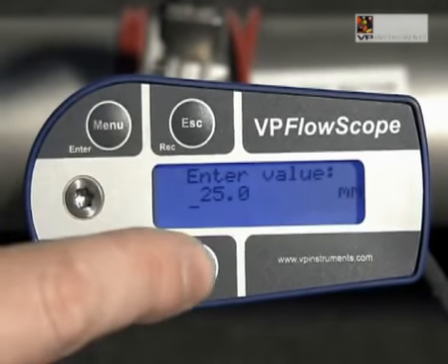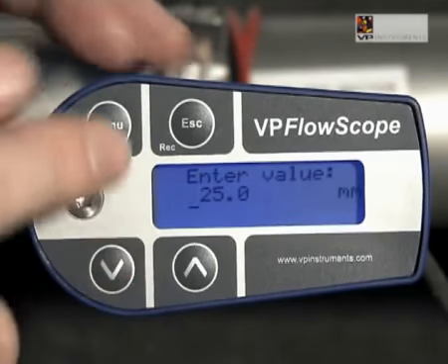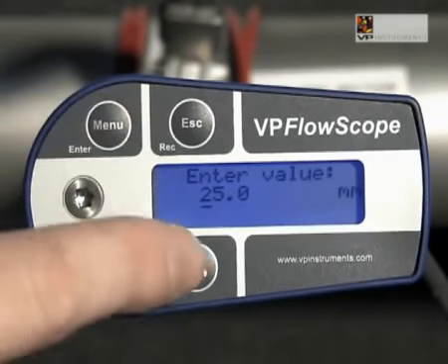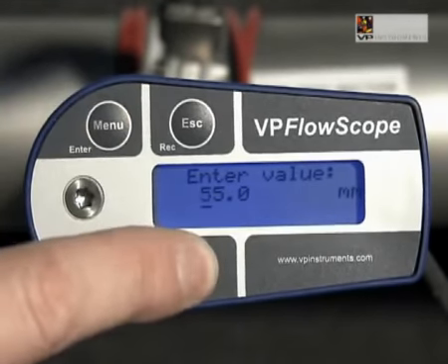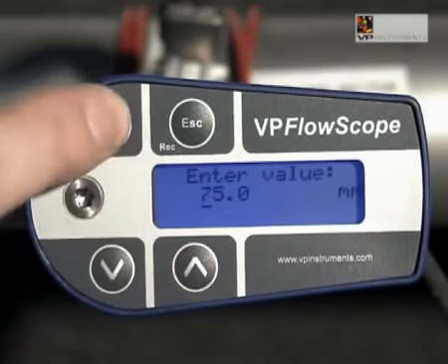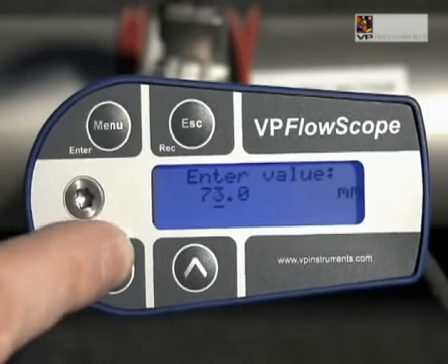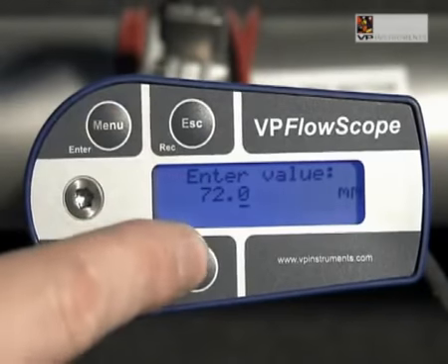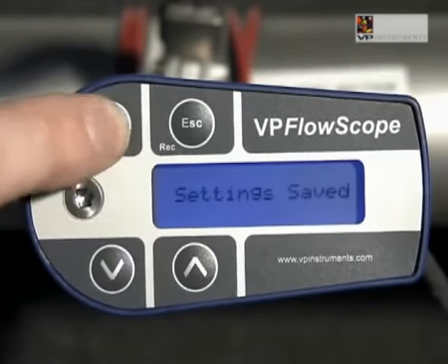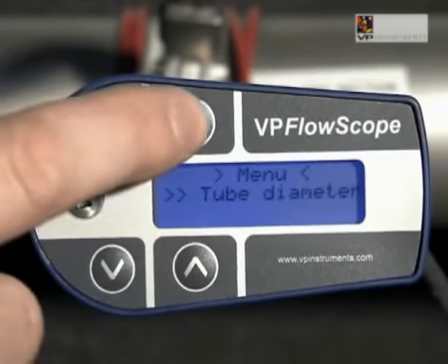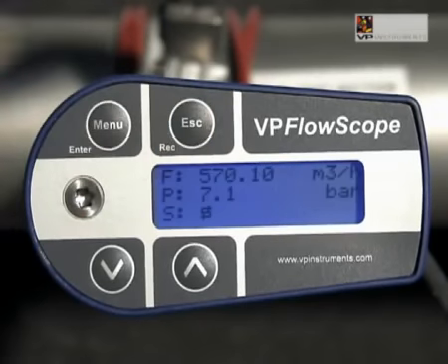The VPFlowScope needs to know the inner diameter to display volumetric flow values. Press Menu and use the arrows to go to Settings. Press Enter and go to Diameter in the menu. Press Enter. Set the tube diameter. Use the Enter Escape buttons to move the cursor to the right or left and use the arrows to change the digit.